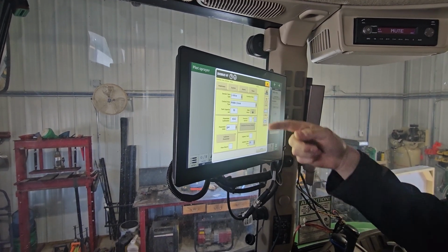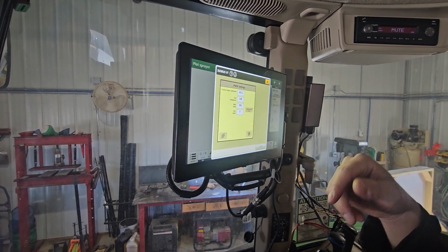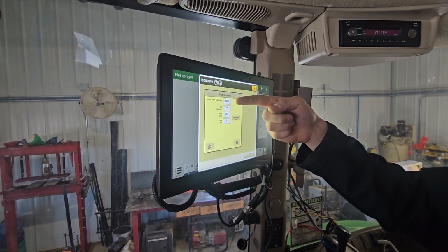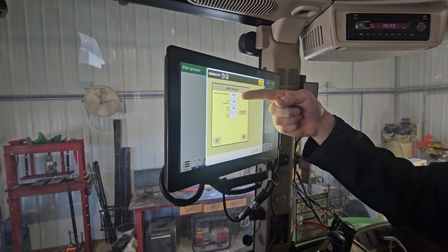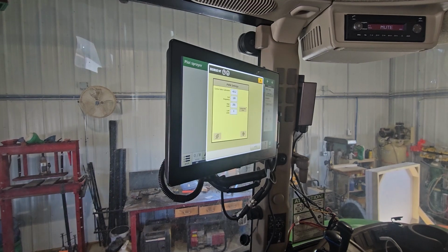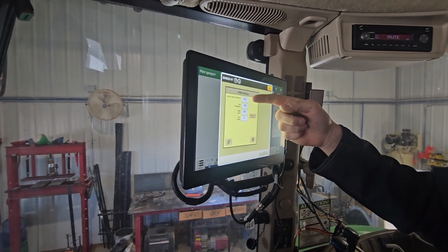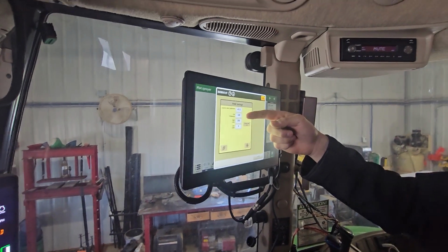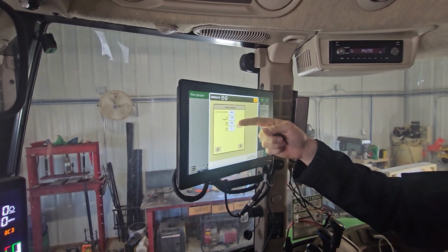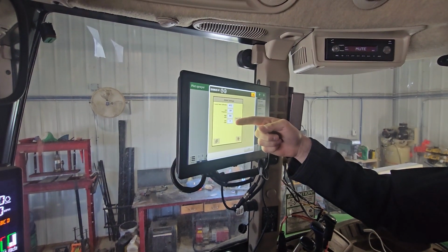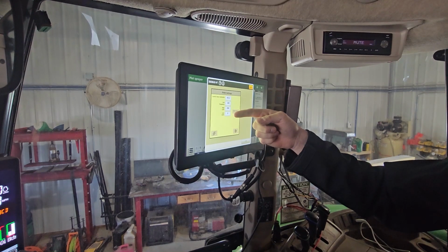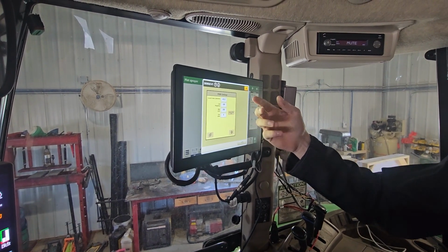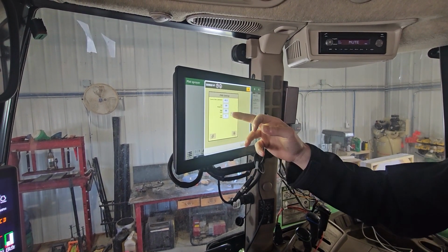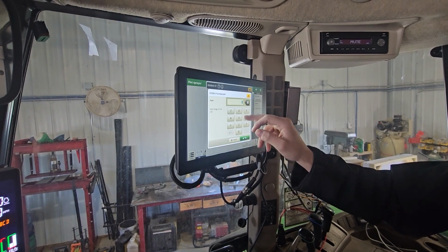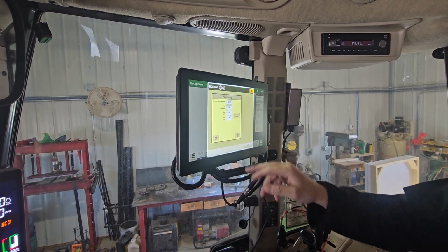Put in your tank capacity there. Under PWM setup, you will have your control valve calibration for a hydraulic pump. Typically it is 4012. The GX2 electric pump, you would put in 9911. Coil frequency will always be 100. High limit will be at 255. Low limit, generally for an electric pump would be 0. Generally for a hydraulic pump, this would be set to, I'd say about 25 to start off with.